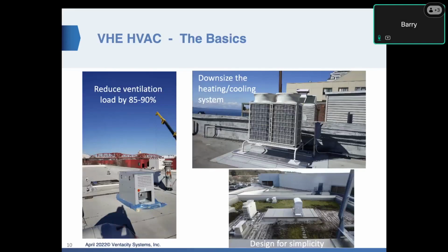This very high efficiency HVAC retrofit is based on reducing dramatically that ventilation load, as I said, and downsizing the heating cooling system, as I mentioned at the beginning, because you have much lower heating and cooling requirements for the outside air, you can use a smaller heating and cooling system. So we're reducing the capacity of the heating cooling system. And then it's designed to be really simple. This is a project we did where we took this RTU off, this bottom right picture here. That's where the RTU used to be, and now it's just a small HRV doing the ventilation and the heating and cooling by the heat pump that's on the left.